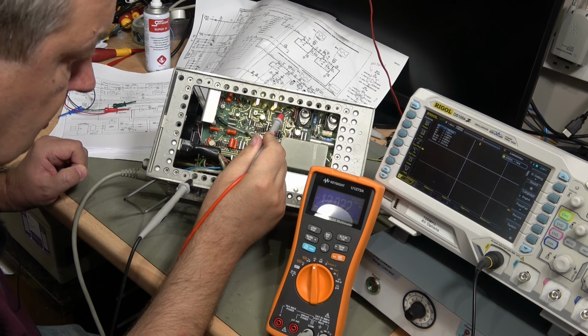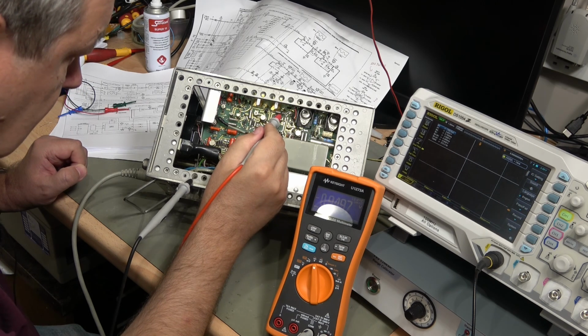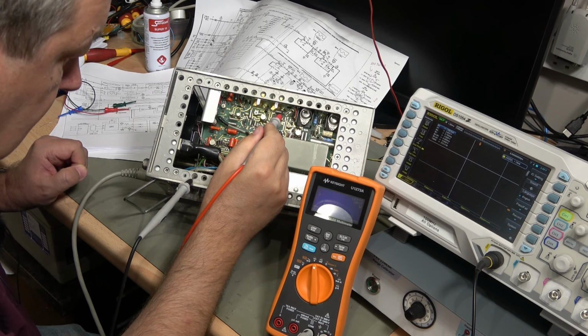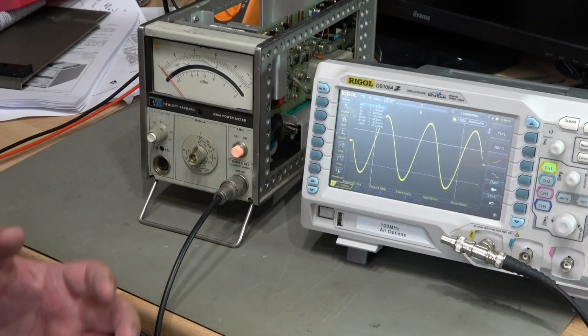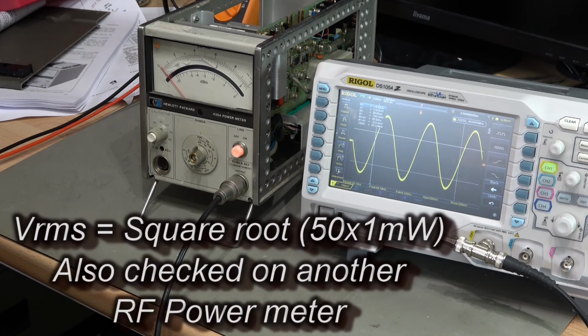Pretty much always, the first thing you do is just check the voltages. They should have been 12 volts, they were plus minus 12.2, so that was fine. And then I checked the reference output, which should be 0 dBm or 1 milliwatt, and that was bang on to within about 0.2%. So I was happy there.